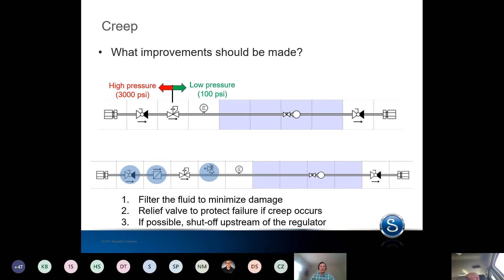Next is adding relief valves. So just downstream with a regulator, it's always a best practice to add a relief valve so you're protecting that system. And we see many people doing this, right? So it's very common. It's absolutely required in some instances too.